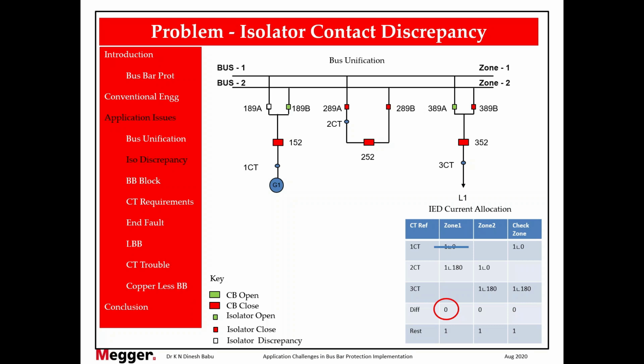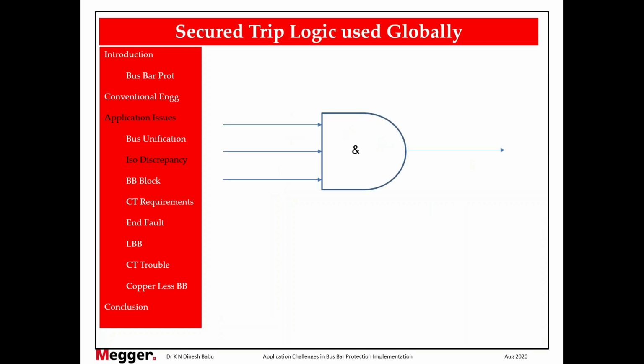The logic goes like this. The trip logic for each zone has a 3 input AND gate. The first input, main zone directional. Second input, check zone non-directional. Third input, bus PT under voltage.